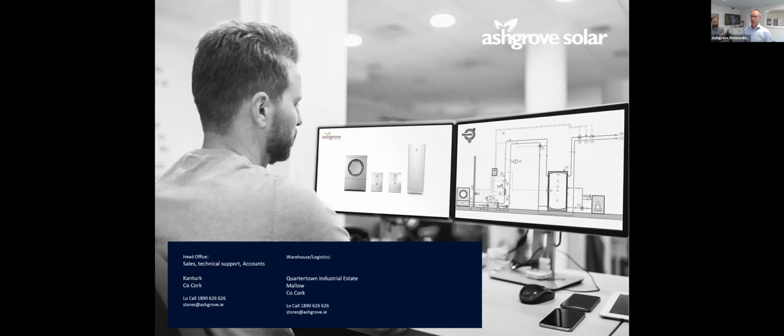There is a thing called a bifacial panel. That's a different thing. A bifacial panel has solar cells on either side of the panel. We would only use that in something like a field, where the sunlight that doesn't hit the panel reflects up onto the bottom of the panel, and we pick up that energy at the back. Okay, that's a bifacial, not to be mixed up with glass. And obviously, if I have that panel on the roof of a house or a commercial building, the bifacial doesn't work because there's nothing being reflected into the back of it. So we wouldn't use that there.